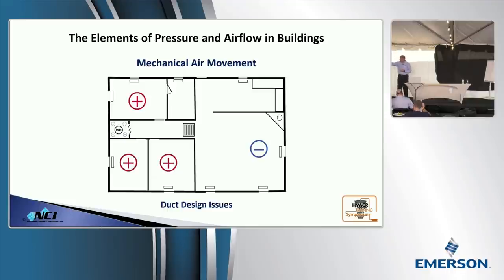So if you're pressurizing those bedrooms that only have supply registers in them, what's it doing to the main body of that house where there's a fireplace and a water heater? It's depressurizing it, right? Pulling it into a vacuum. And air takes the path of least resistance. So it's going to pull air from wherever it can get it. What are the two paths of least resistance in the house that we're looking at here? I'll give you a hint. We got a fireplace and we got a water heater.